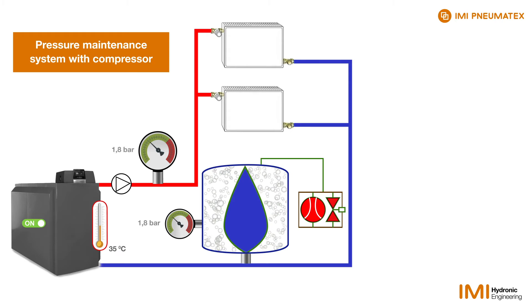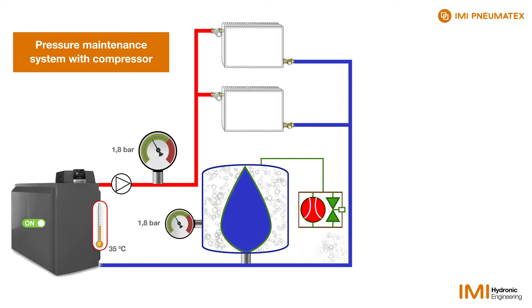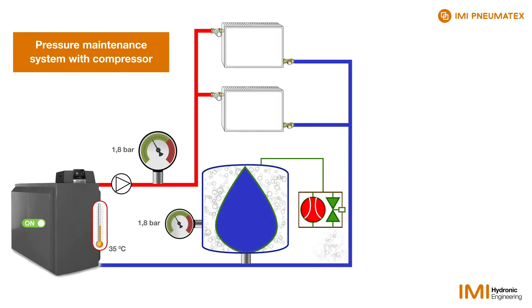A dedicated controller detects this change of value and opens a valve so the pressure can escape and the butyl bag can continue to be filled with water. The vessel is filled until the pressure drops down to 1.6 bar. Then the valve closes again.